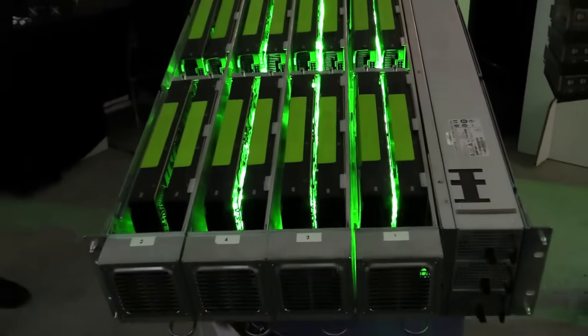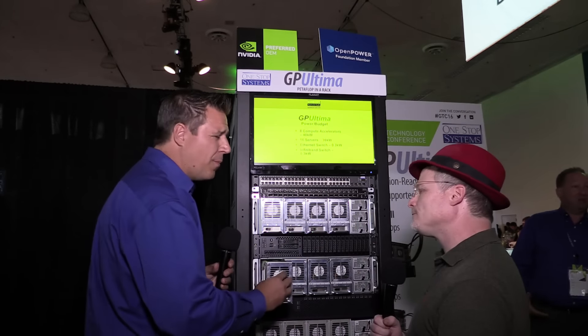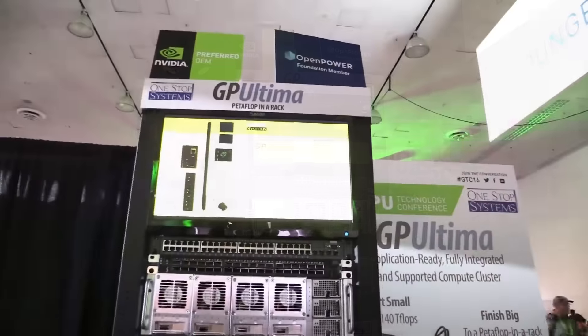Okay, that's a lot of compute power in a small, dense space. How do you keep that cool? That's a good question. We have a couple of different cooling options. Air cooling is preferred — we have a very high-powered fan in the front that pulls the air through and sucks it out the back. If you get above 32 degrees Celsius, we start looking into a liquid cooling option, either in the canister or in a rack itself that has a controlled environment.